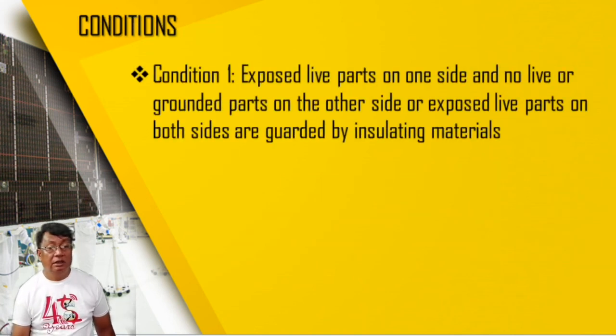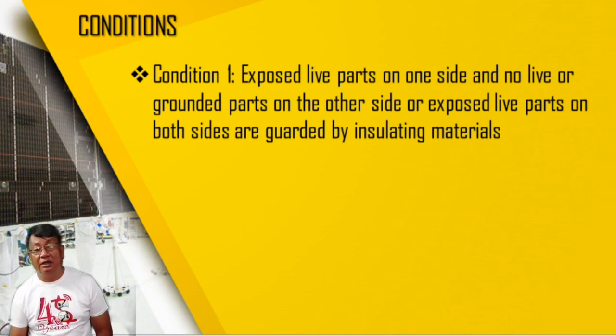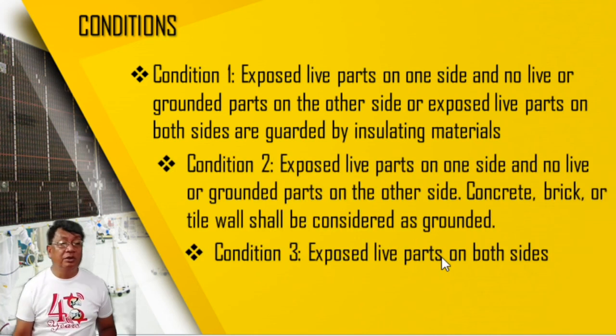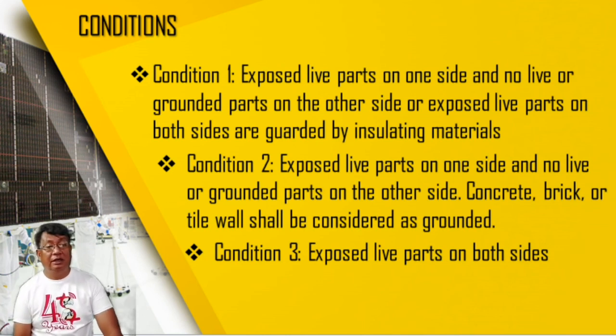Conditions. Okay, so we have condition 1: exposed live parts on one side and no live or grounded parts on the other side, or exposed live parts on both sides guarded by insulating materials. Okay, so we have condition 2: exposed live parts on one side and grounded parts on the other side, such as concrete, brick, or tile, which shall be considered as grounded. Okay, so we have additional grounding system. Okay, condition number 3: exposed live parts on both sides. Exposure of the live parts on both sides.